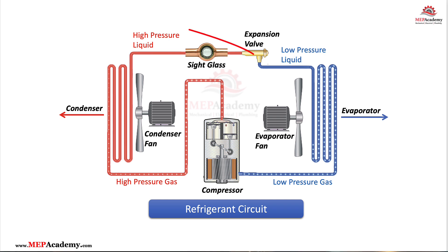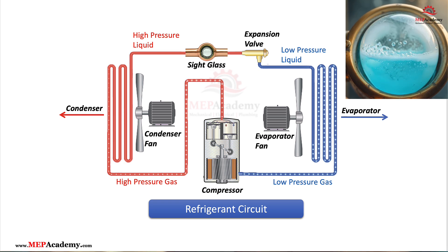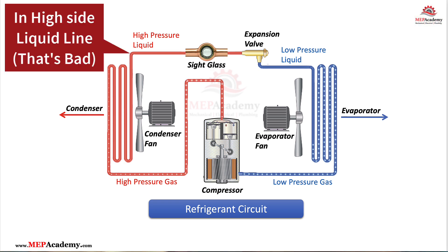When high-pressure liquid refrigerant exits the metering device and enters the evaporator at a much lower pressure, it can't stay in liquid form. The drop in pressure causes part of the refrigerant to boil instantly, absorbing heat in the process — that's flash gas. But flash gas can also form where it shouldn't: in the liquid line, if the refrigerant pressure drops too early. That's a red flag.